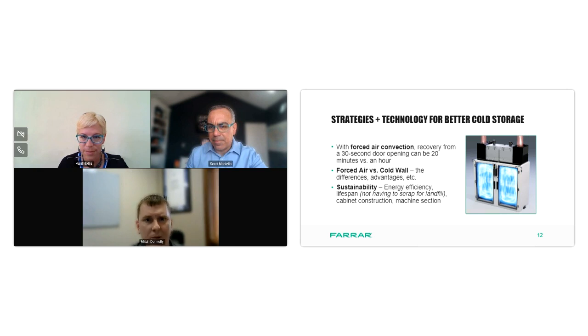We've seen that forcing air through the freezer helps with uniformity, and it helps with recovering from a door opening. So when you let the air out, warm air rushes in and the cold air falls out. When we shut the door, having the ability to force air through the system allows it to recover much faster. And from a performance standpoint, because of the capacity inside of it, you're able to take warm product and put it inside the freezer and let it come down to temperature without risking damage to the compressors or any of the refrigeration components.